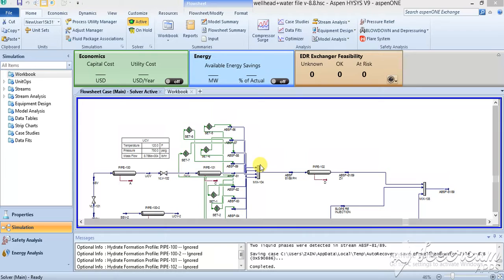There will be a bypass out of the production manifold from every individual wellhead that will be going to the test meter. That test meter basically determines the physical properties like the density, gas oil ratio, and all those things in that particular line. It can be the Coriolis meter or some other meters. It can be the multi-phase flow meter. Those are used for the physical property measurements, and you will come to know how much sand, how much water, how much oil is coming out of the stream or the pipeline.